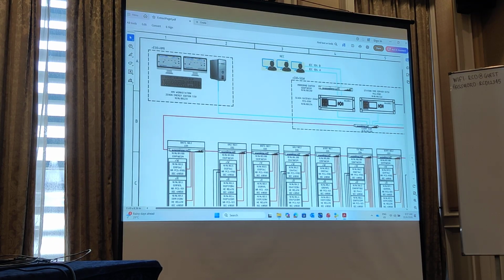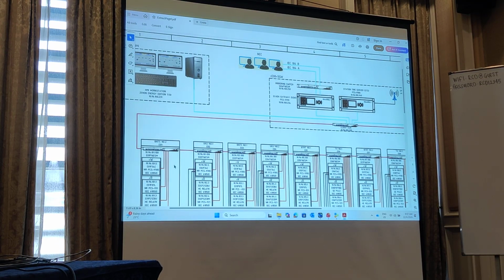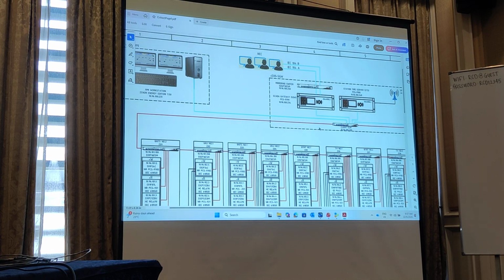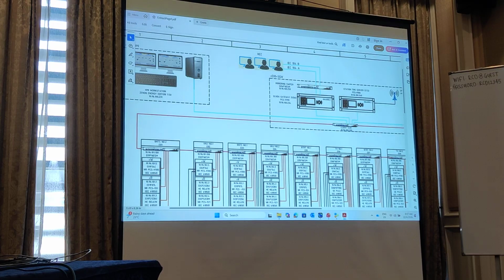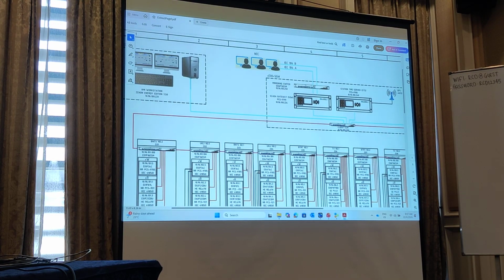Okay, and then over here, below the downside, below the ESM on the server side, we call this horizontal communication, where all the relays communicate with each other. So here I can separate them into two different 61850 terms: one is by MMS, another one is by Goose.